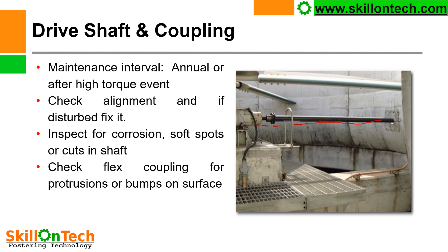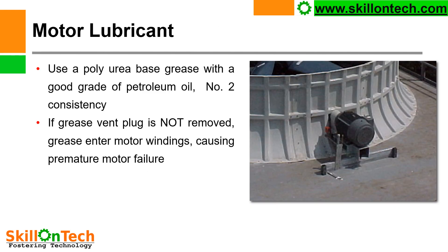Here you can see a VFD or induction motor. For motor lubrication, use a polyurea-based grease with a good grade of petroleum oil, number 2 consistency. If the grease vent plug is not removed, grease enters the motor windings, causing premature motor failure. Therefore, while putting grease into the motor, take care to remove the vent plug.